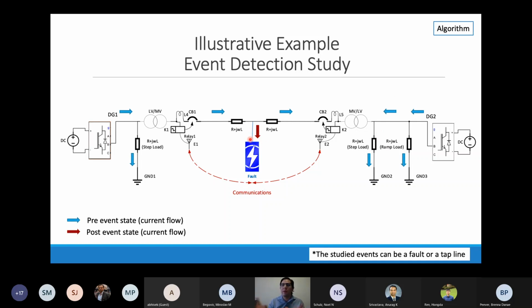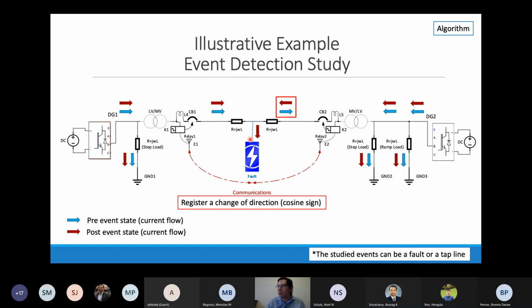So how will our relays be able to detect this based on the rate of change of the cosine and the sine? These are the post-event state current flows that we have. As we can see here, we register a change of direction, which the relay of the second end sees, but the relay of the first end does not. So they need to be able to talk to each other in order to say, okay, there is a fault here, or there is a tap load, or whatever event is happening.